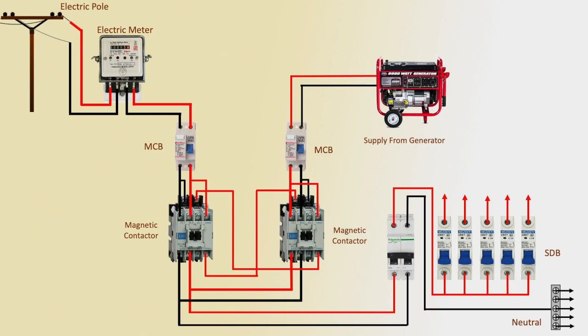When the first magnetic contactor is ON, the second magnetic contactor is OFF; when the second magnetic contactor is ON, the first magnetic contactor is OFF. This is a very simple anti-lock interlock system — meaning it is not possible for both magnetic contactors to be ON at the same time. Thank you.